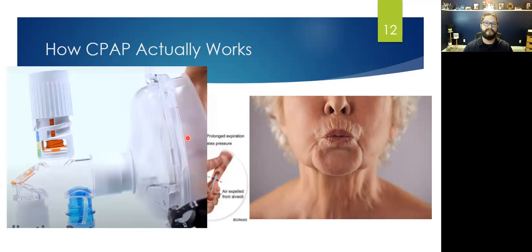And what's neat about your system, this is the system you guys use, and I'll give you a little bit on how it works. Air and oxygen come in from down here. This part right here is an anti-asphyxia valve. And when air and oxygen are pushed through, it flips open that anti-asphyxia valve because they're breathing from here. It goes in through that same little hole we talked about before, and it's flowing at a really high flow rate. So we'll go through more of that in a minute. But when they breathe that in, they exhale, they breathe against that, and then they're breathing against this exhalation valve. And this is what differentiates your CPAP from every other CPAP on the market. All the other CPAPs just have an exhaust port, and they're relying on this pressure and flow rate to create what that person's breathing against.